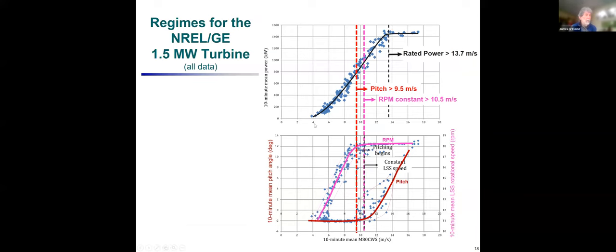The power curve shows rated wind speed is reached at about 14 meters per second, but pitch kicks in at around 10 meters per second, and pitch interferes with the correlations we're interested in. So essentially all of the data we analyze is in region two, at speeds below about 10 meters per second. RPM reaches a peak at about 10.5 meters per second.